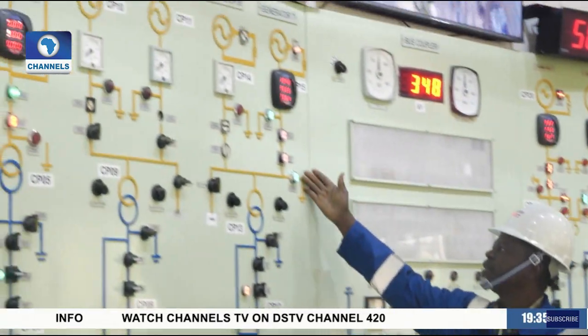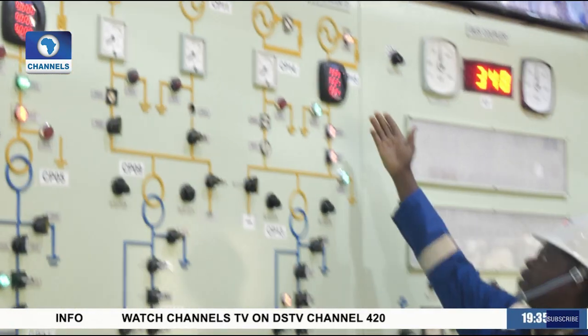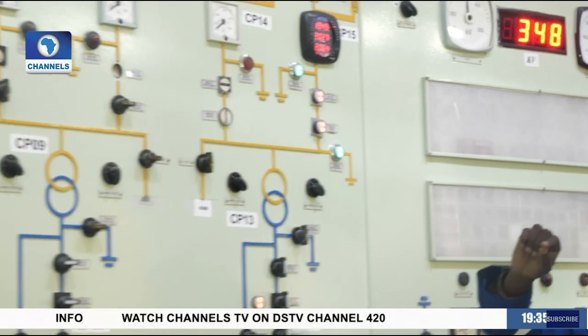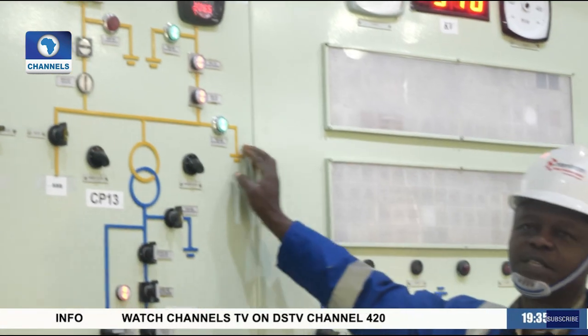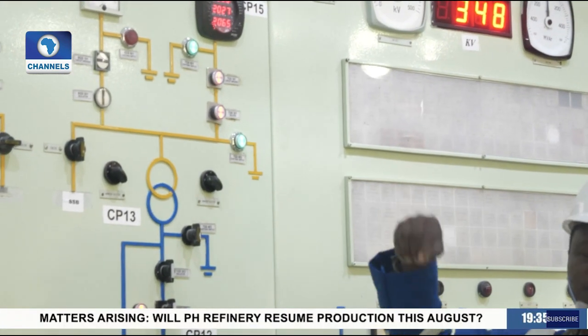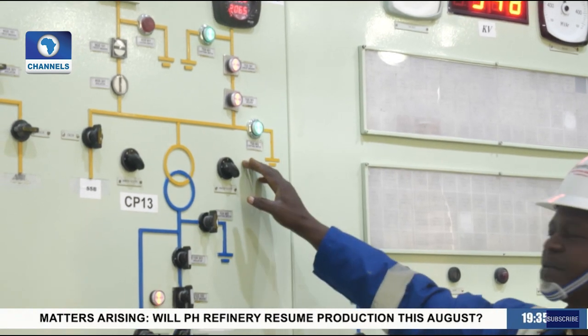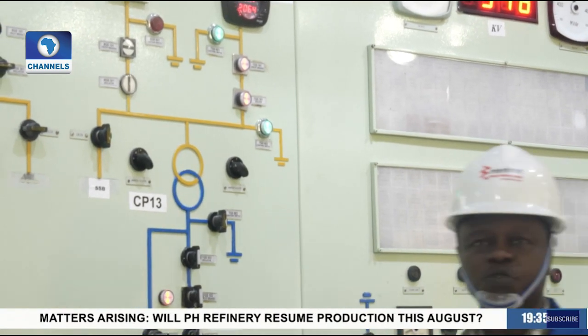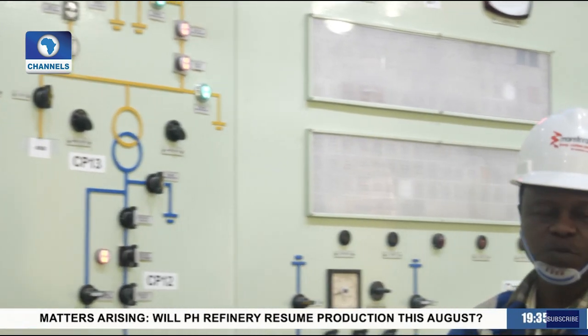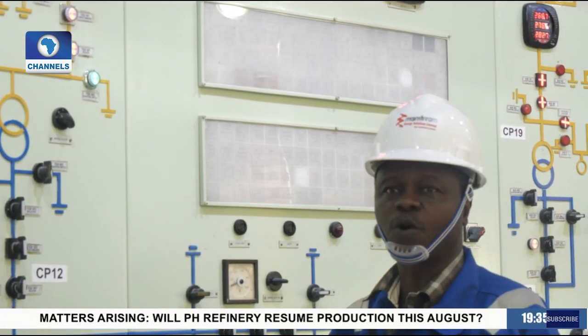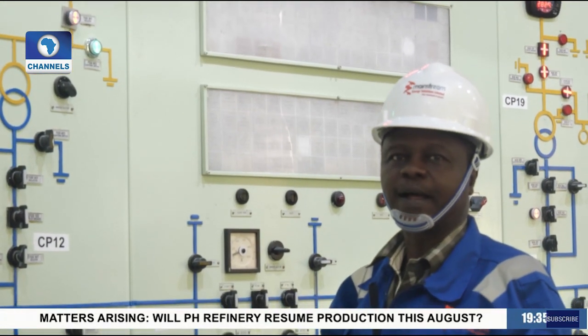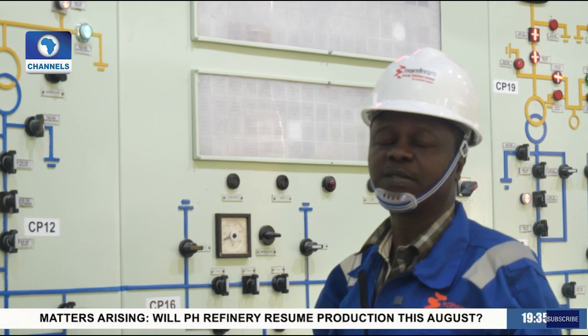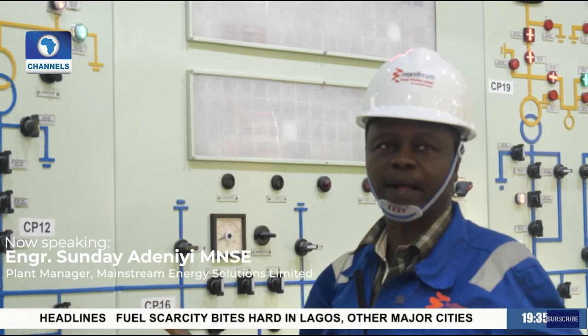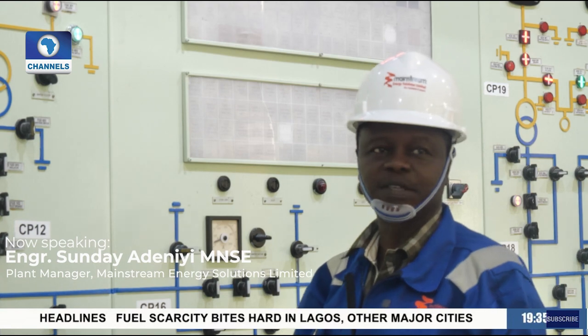In voltage generation, each unit generates at a voltage of 16 kV, which is the terminal voltage of the generator. So what comes out of the generator is 16 kV. But that is not what goes to the grid because of what we call the losses, and losses are a factor of current. We want, as much as possible, to transmit our power at a very high voltage and low current so that we can minimize the losses.